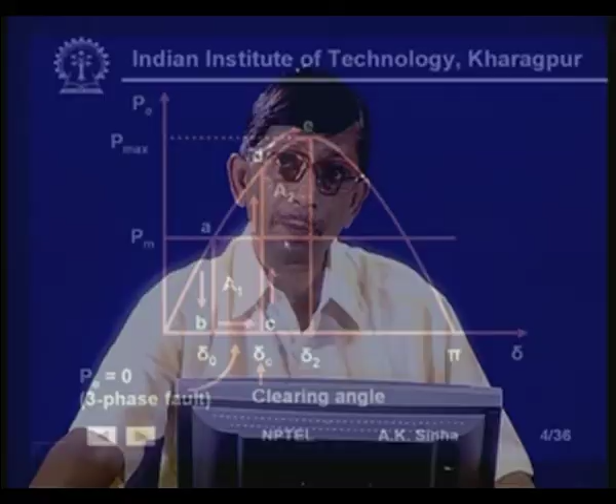Now, there is a question which comes: suppose we do not open the circuit breaker at this point delta c, but we allow it to move further, that is, the action of the relay and circuit breaker takes longer time. Then what happens? This point C will be shifting further on this side, which means the accelerating area will become larger and larger, and if that happens, then the maximum decelerating area which we can get will be up to this point only, that is above this line, and up to this point is what we will get as decelerating area.